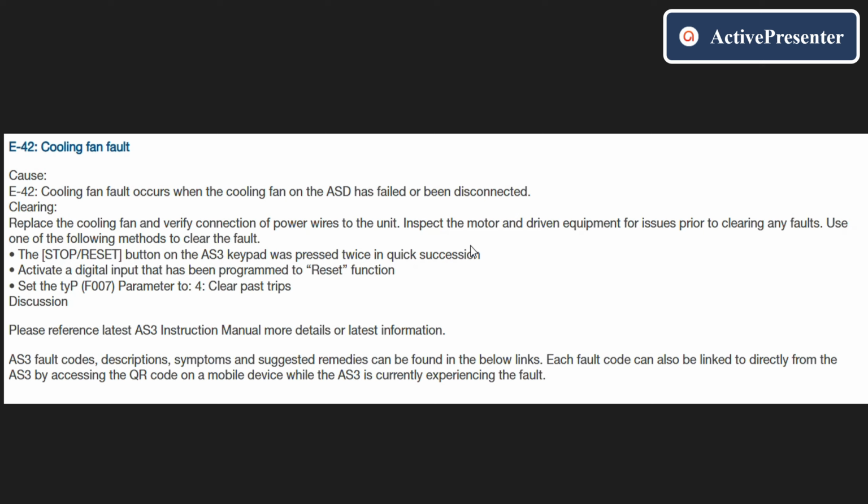In that case, there are more chances that the issue is because of the connector or there could be another issue. And if you found everything is okay, like the fan is also working, there is not too much dust inside and all, and this error is still coming, it means the reason could be an issue inside of your VFD. So for that you just need to repair it, and other than that we don't have much option for this.